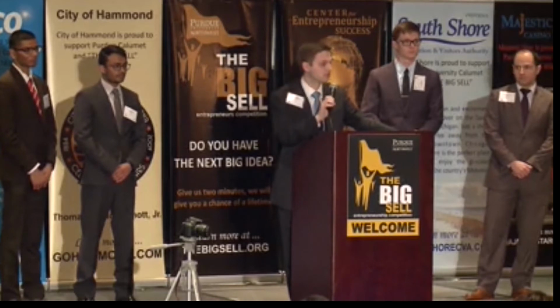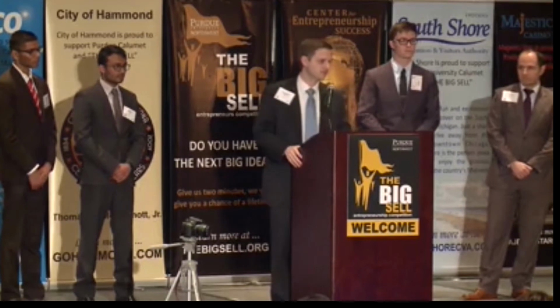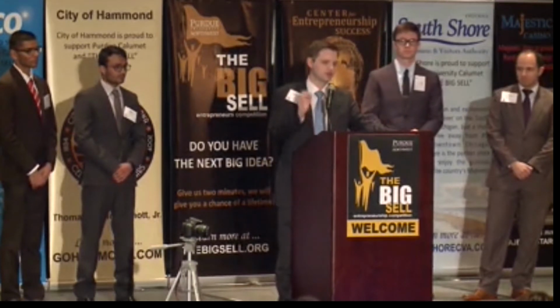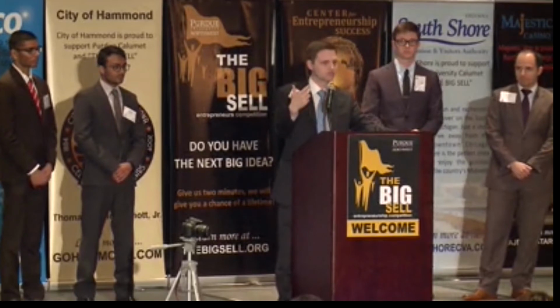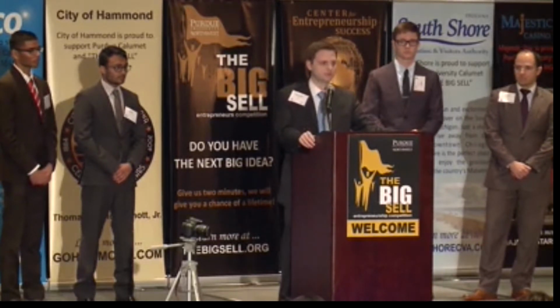So what type of approvals do you have to have for this? I'm sorry, say that again? Does this require FDA approvals? Yes, it would. This would be a Class 2 device, is our expectation. It's not an implantable device. It's not what would typically be a Class 3. So we're estimating it should take about 6 months to get FDA approval, which is pretty much the typical for a Class 2.